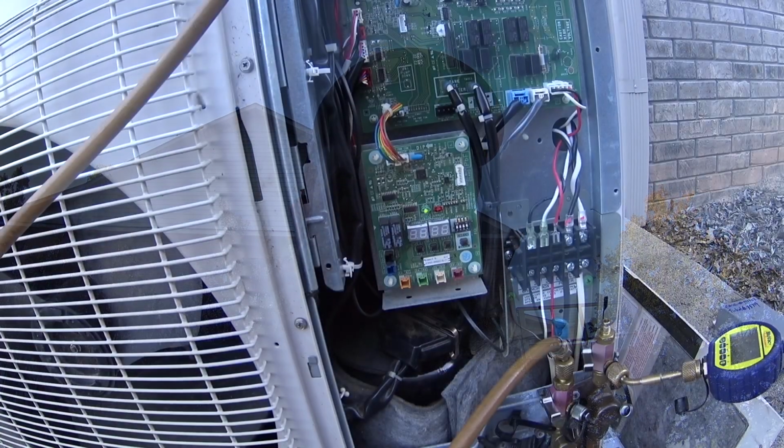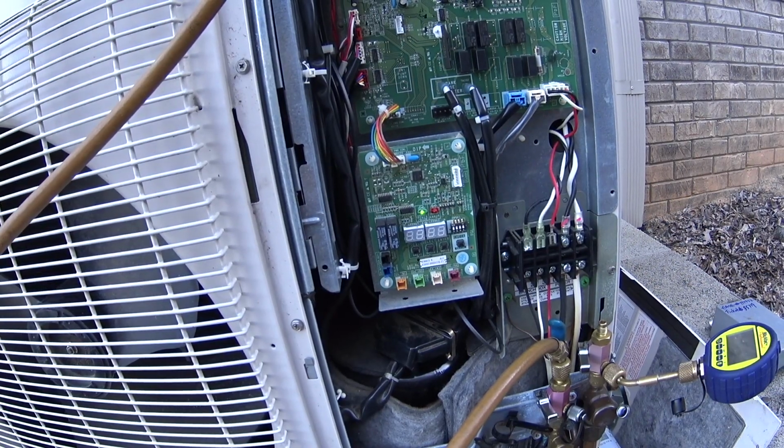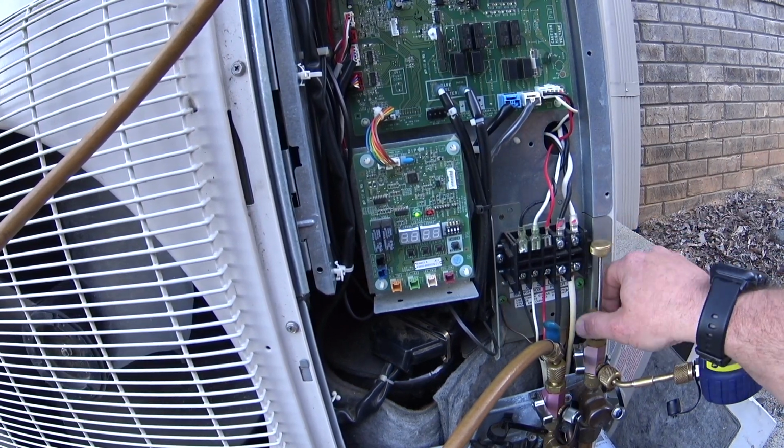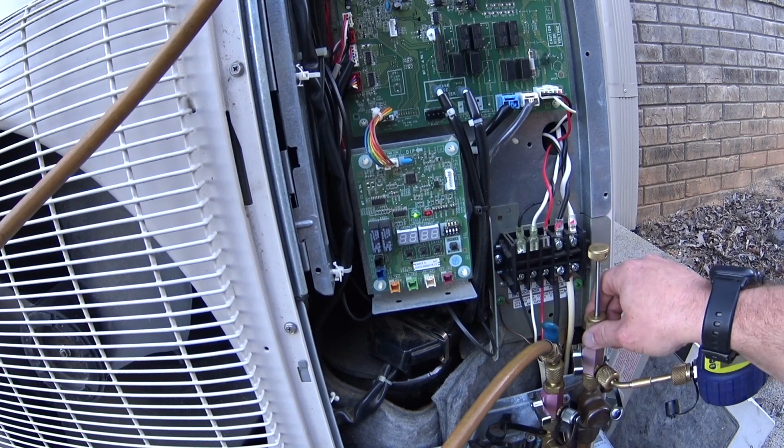The system took 6 or 8 ounces before I was able to clear the scale, because I forgot to zero it out before I started adding. But anyway, we've got sufficient charge in it, so I'm going to see if I can get this powered back up and run through another check mode. After all is said and done, we're going to go ahead and recommission the system with another check run.